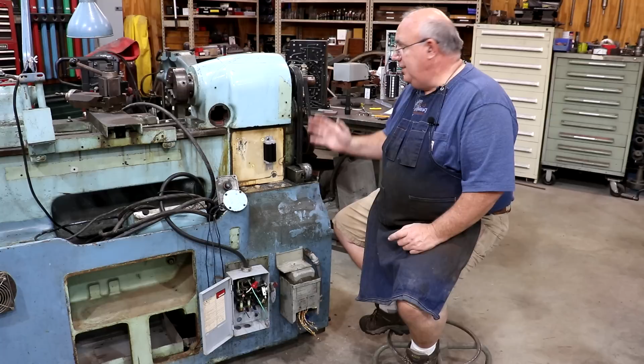Let me explain what controls we want to use on the lathe to control that board, power it, and so on. First off, we've got a power disconnect down here, just a fuse disconnect. It's already wired up coming into it, we'll use that existing wire, which goes through some fuses for protection, and then coming out we'll have our 220 volt power system: L1, L2, and ground coming in from the power supply here in the shop.